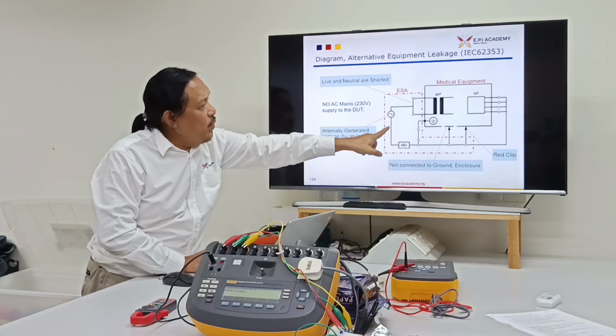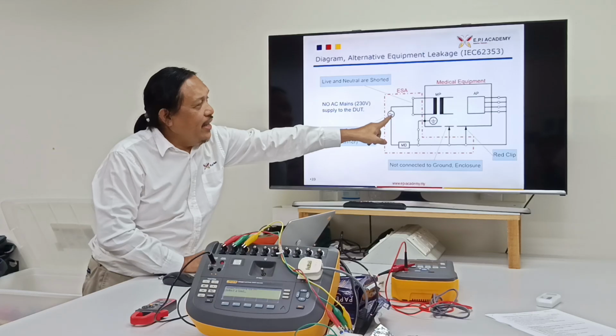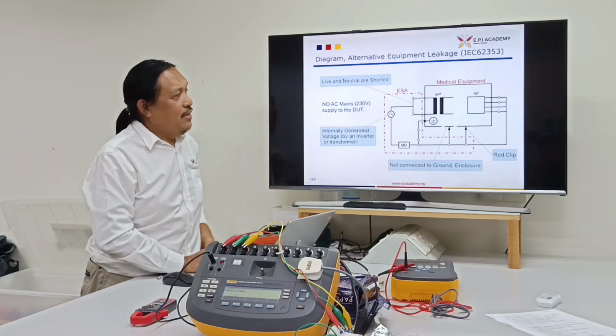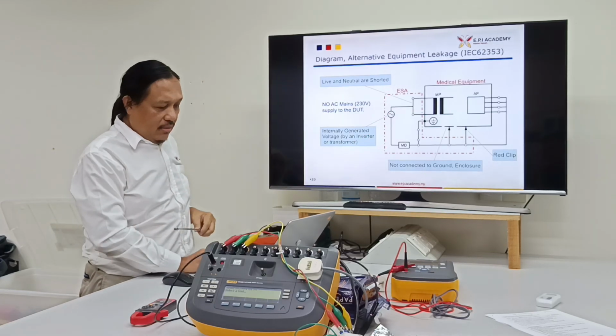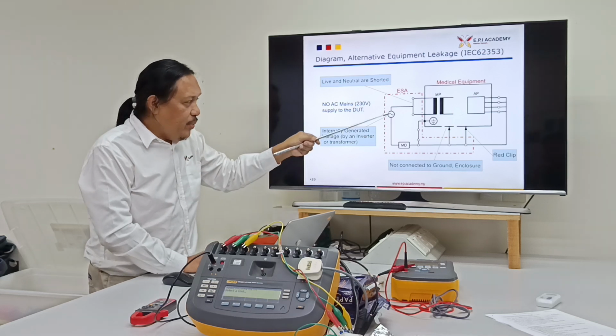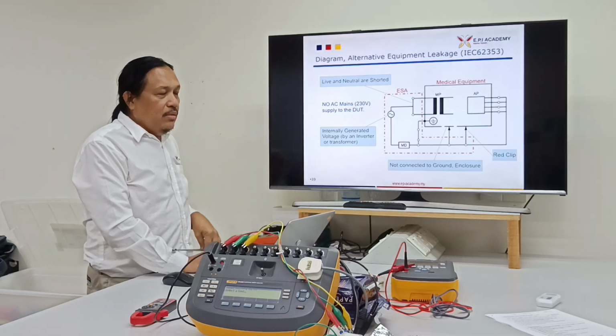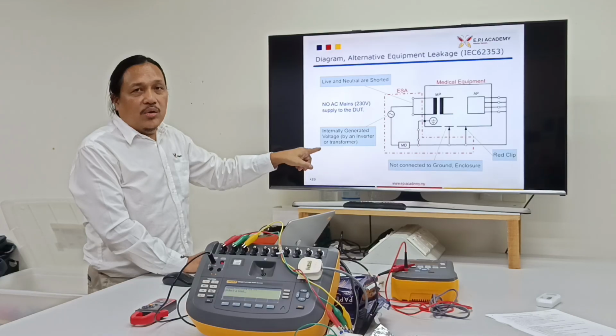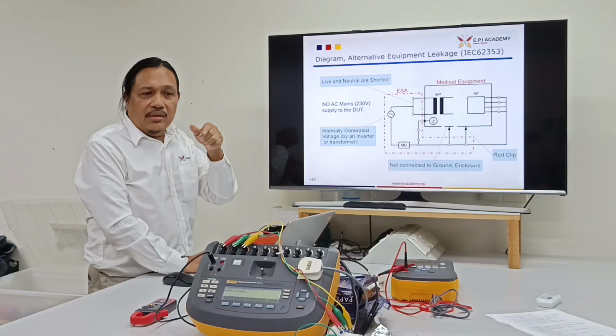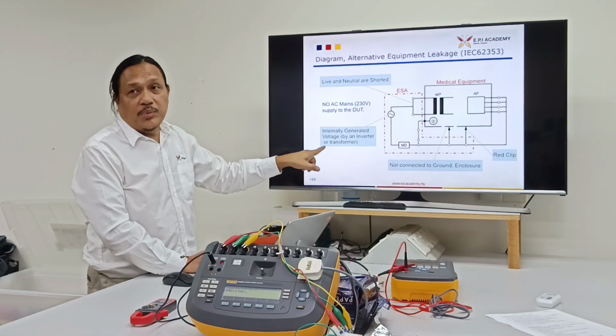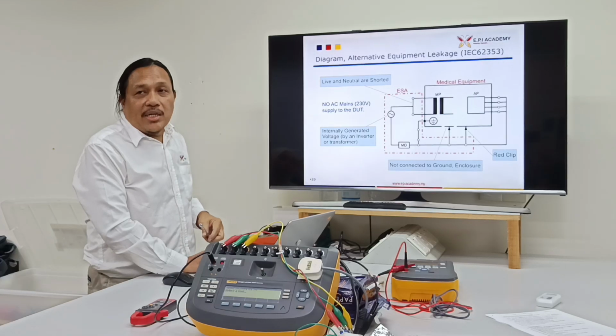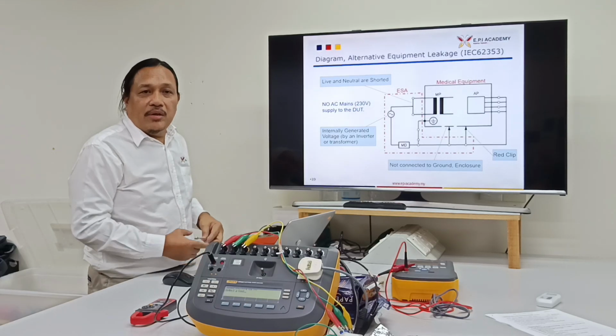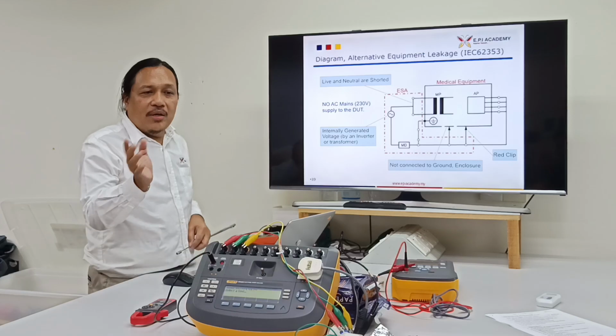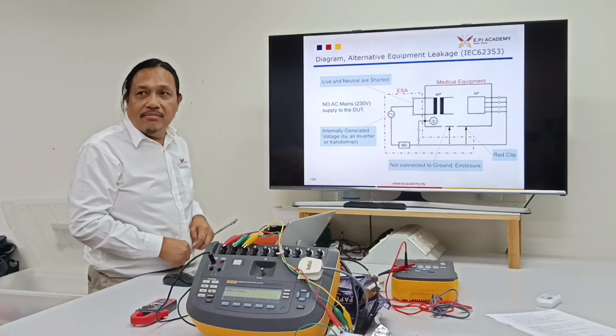What this analyzer will do is just send a test voltage. This voltage, this symbol, is from an external source, which can be either generated or made using a transformer. This Fluke uses a transformer. The other brand, I don't know. I have not opened the equipment of the other brand yet, but the Fluke I have opened and know what's inside.